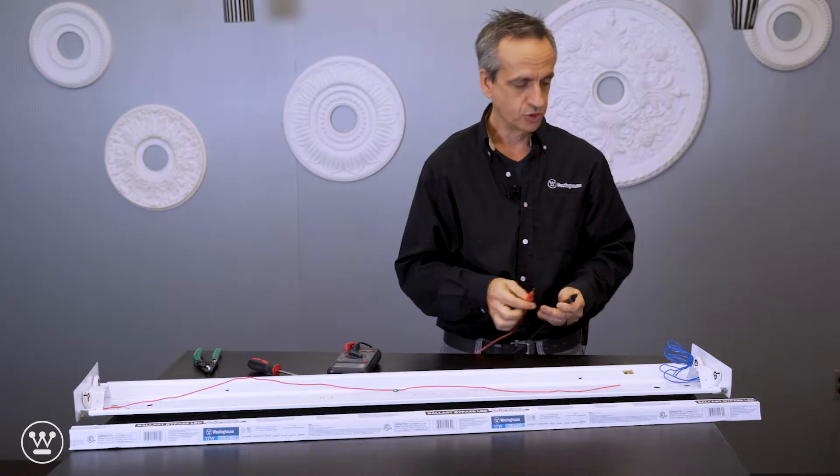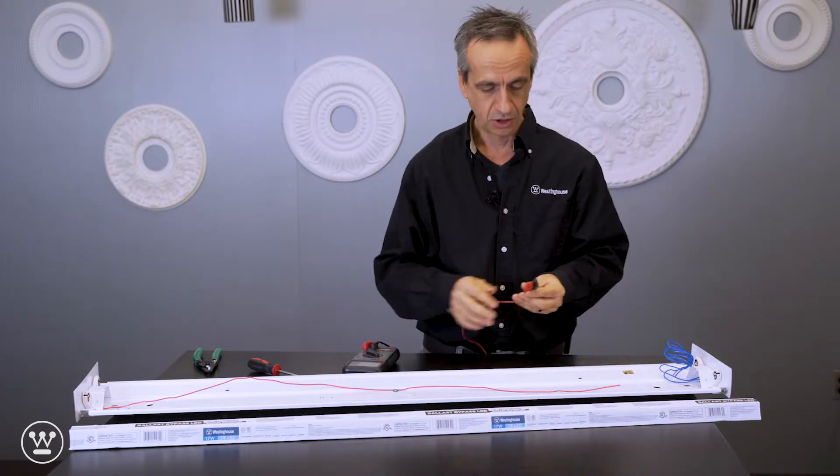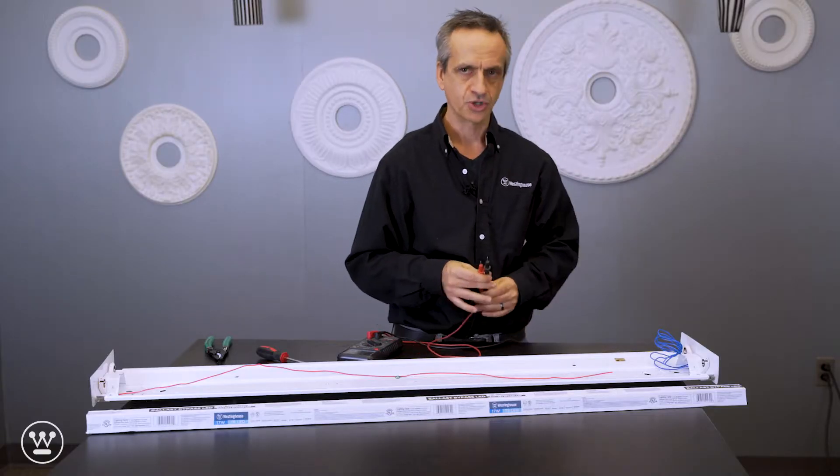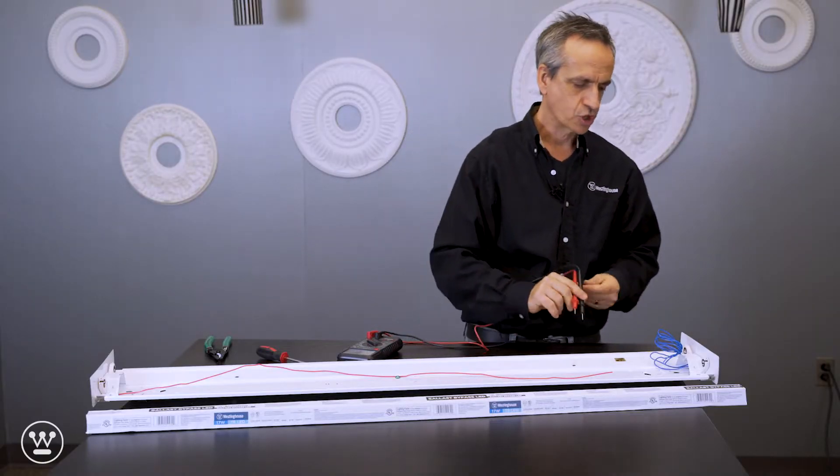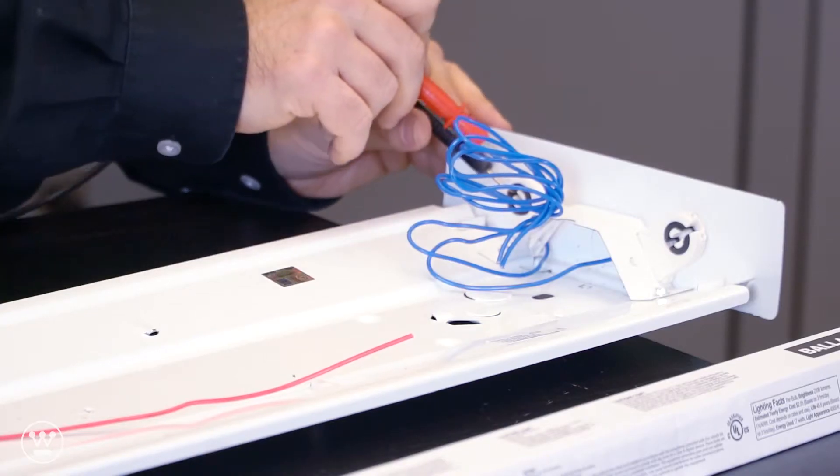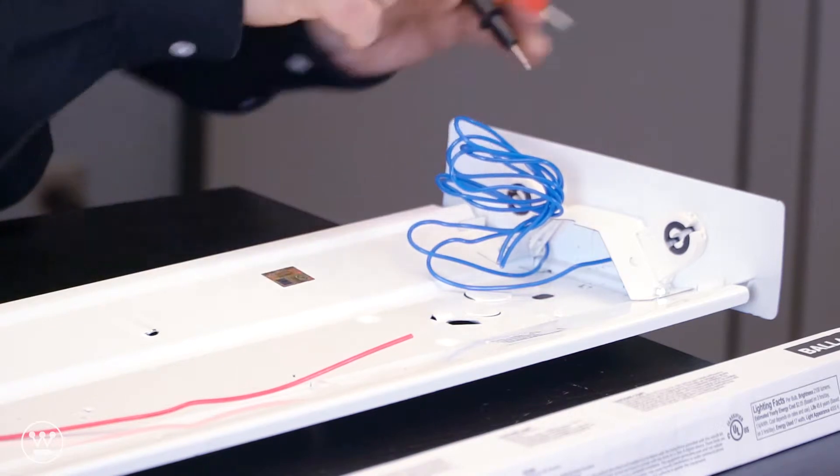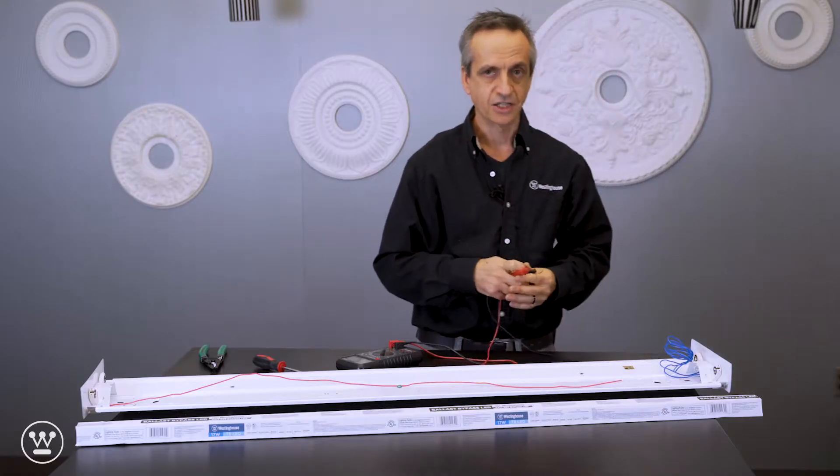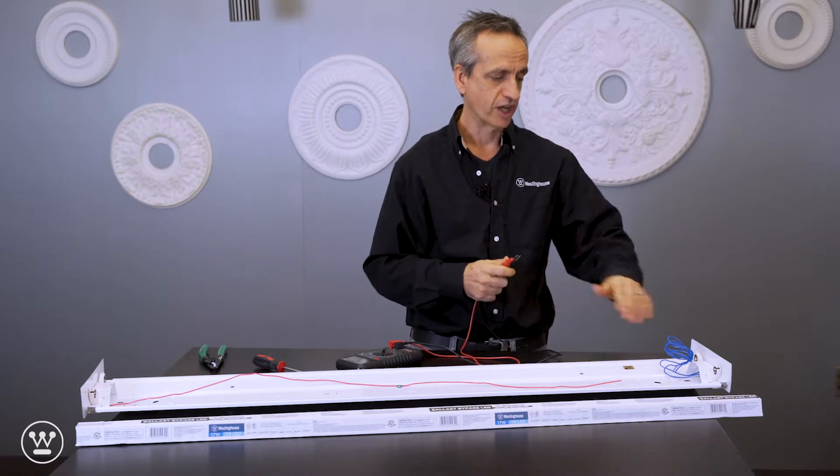The best way to do that is with a meter, checking for continuity. We're going to check for continuity on the tombstones or sockets. We want to make sure that these are non-shunted, meaning non-continuous. These sockets or tombstones are shunted, so we're going to have to replace them.